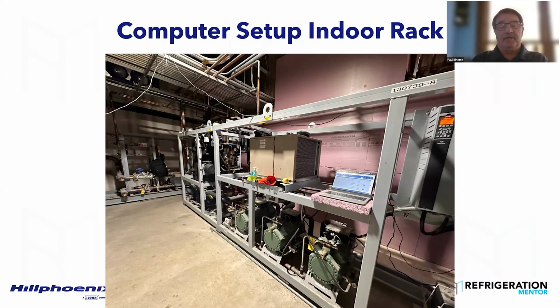Well, I learned way back in the beginning when I first started showing up on these job sites to get in contact with the contractor, because the vacuum needs to be done, pressurization is done, the rack needs to be under CO2 pressure, the cases all need to be communicating online, all the electrical peripherals need to be attached. So when I'm on site, I can concentrate on getting this rack started, testing all the systems, and checking alarms through the week. Because if I do a startup on Wednesday, because we're troubleshooting Monday and Tuesday, we don't get a lot of time in the rack, and that's not good.